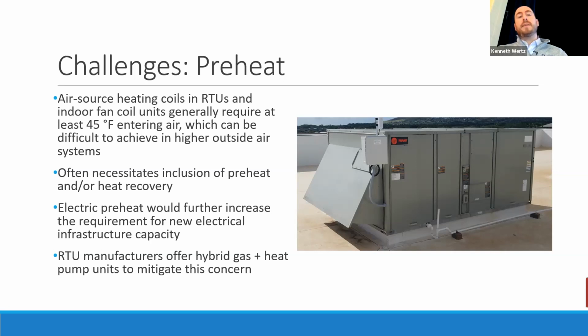So if you fall below that, then the systems either don't work as well or are much less efficient, or can't keep up. So you might have to install a second heating coil, whether it be electric or hot water. In some cases I mentioned here, the manufacturer can provide you a unit that has gas that can provide a little bit of supplemental heat, but then you're stuck on gas as opposed to trying to get to that full electric option.